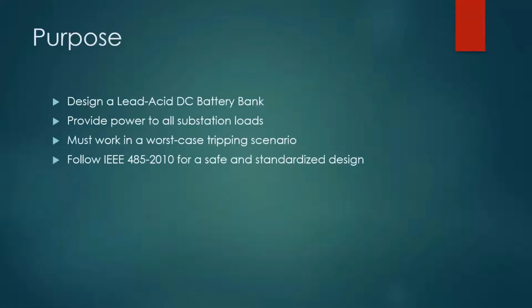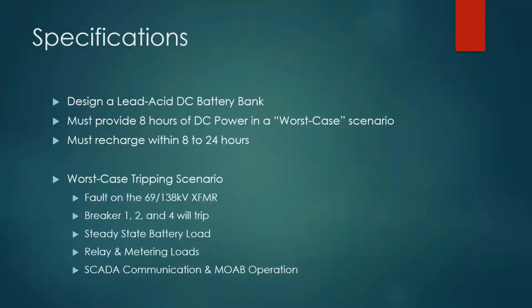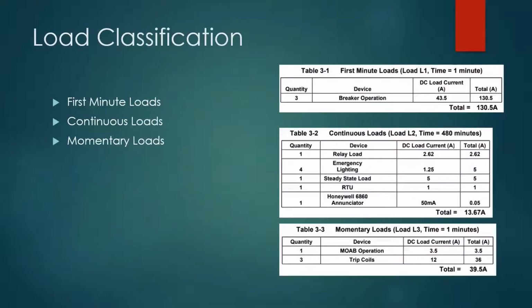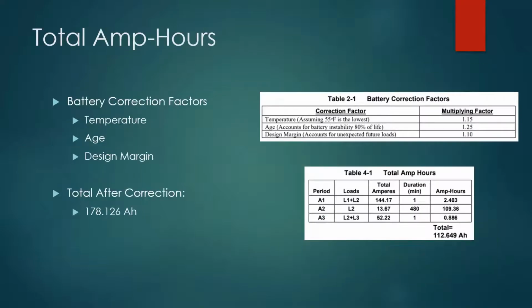I'll be going over the DC battery study. Our purpose is to design a lead-acid DC battery bank to provide power to all the substation loads. We must provide power for 8 hours in a worst-case tripping scenario and be able to recharge those batteries within 8 to 24 hours. Our worst-case tripping scenario would be a fault on the transformer causing breakers 1, 2, and 4 to trip. Our load classification can be seen on the right, including our first minute, continuous, and momentary loads.